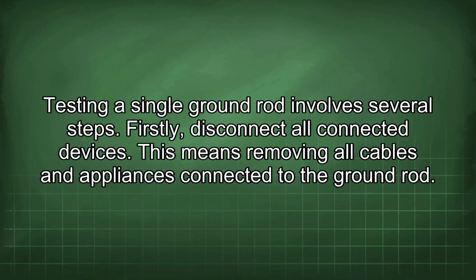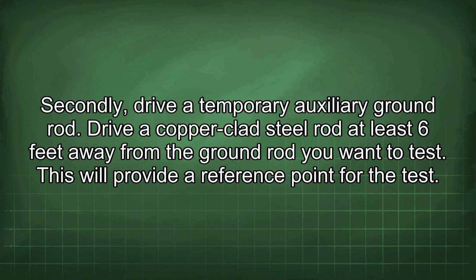Testing a single ground rod involves several steps. Firstly, disconnect all connected devices. This means removing all cables and appliances connected to the ground rod. Secondly, drive a temporary auxiliary ground rod. Drive a copper-clad steel rod at least 6 feet away from the ground rod you want to test. This will provide a reference point for the test.